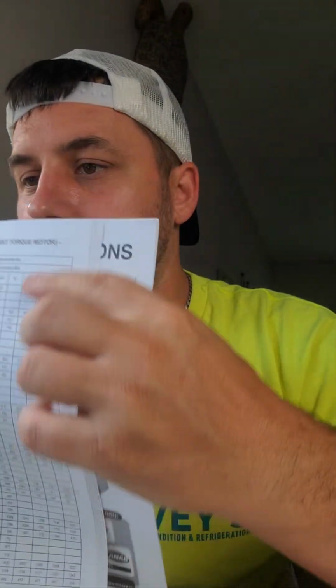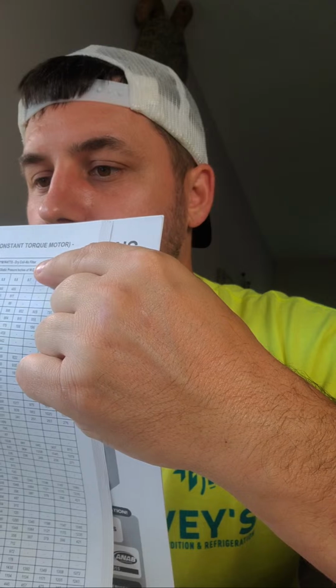Page 36. In the manual, they give you a 3-ton. They give you two ways to look at it, with no heater and with an 18 kW strip. So you're actually going to fall in the middle, depending on what kind of heat strip you put in there. We put in 15 kW, so I just used the 18 kW numbers. But if you look, it shows it as a dry coil. We do 5K. Well, if you do 5K, it'll be closer to the no heater.